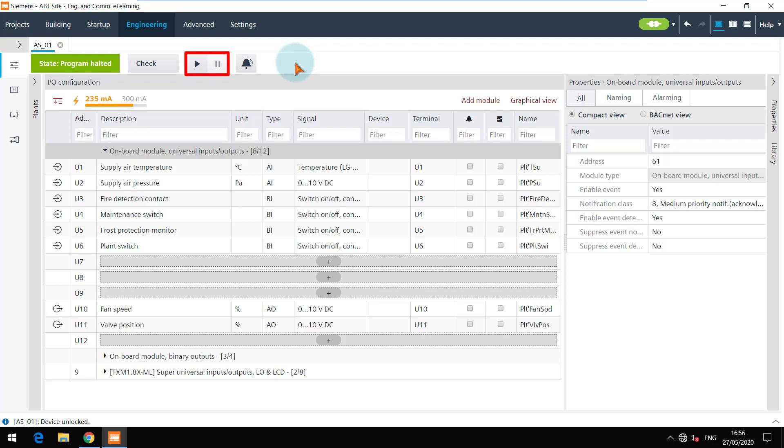As soon as the device is configured and assigned, the play and pause function can be used even before a full download. But it is recommended to perform a full download from the startup tab and then use the play and pause function for delta downloads.